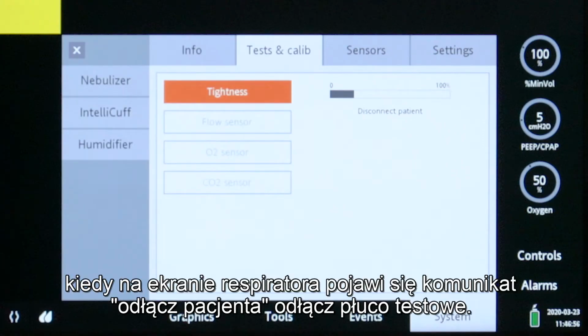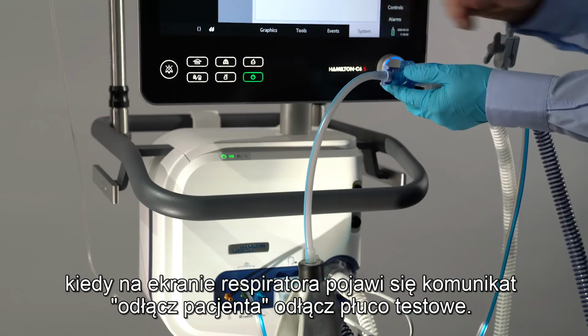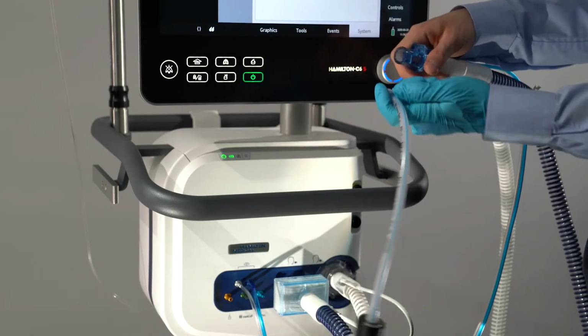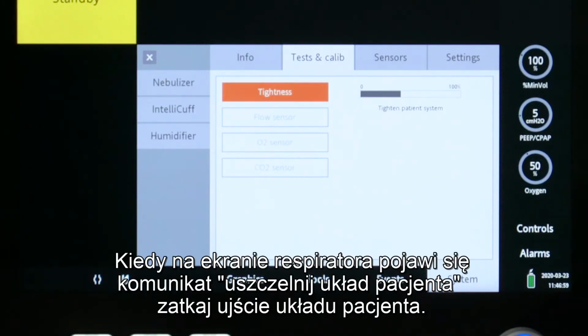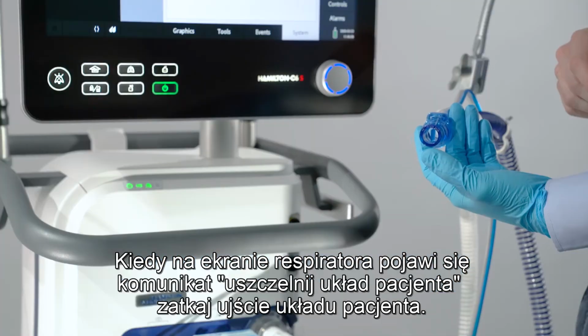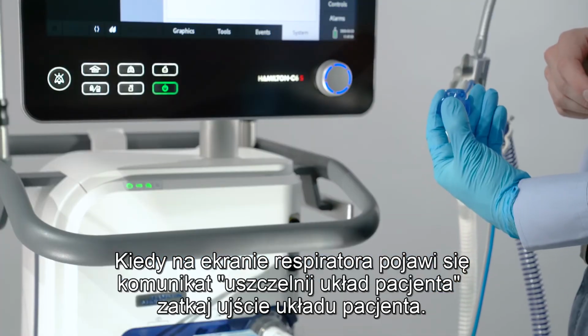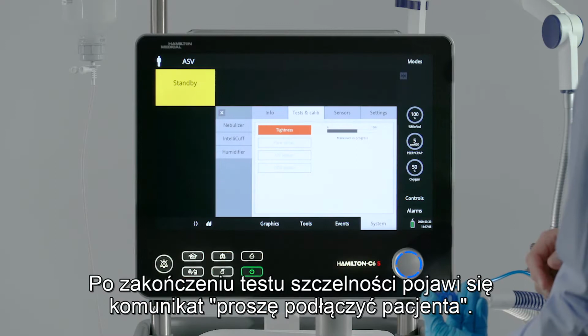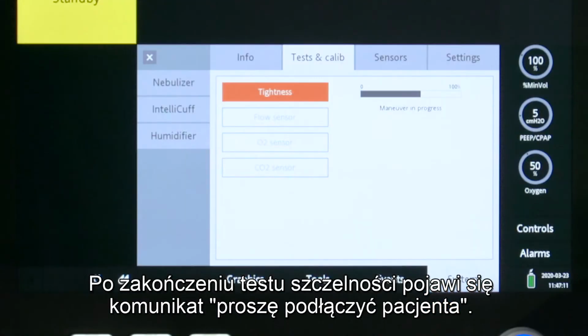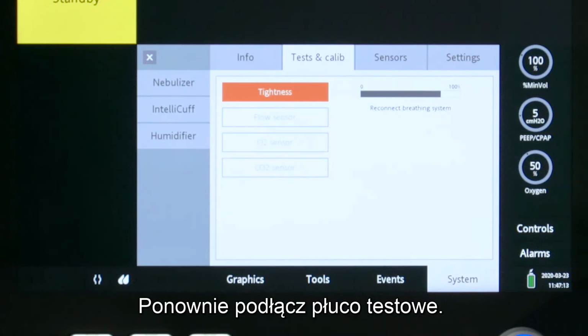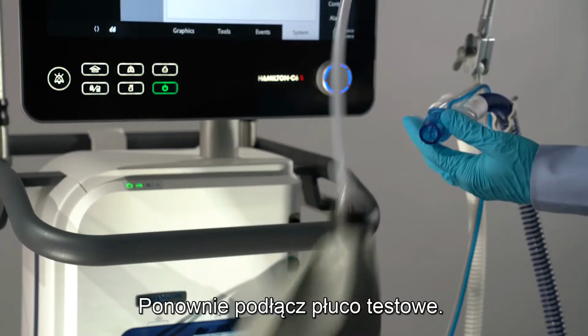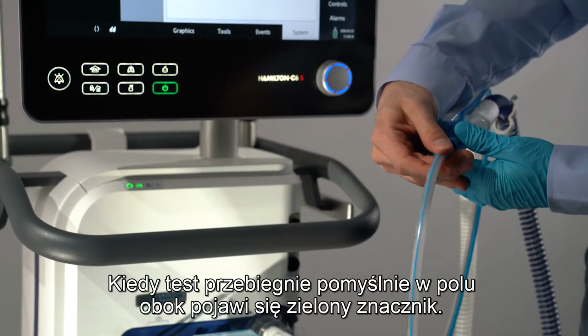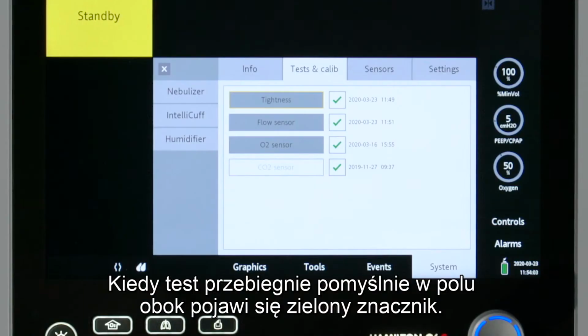When the disconnect patient message appears, disconnect the test lung. When the message tighten patient system is displayed, block the opening. After completing the tightness test, the message reconnect breathing system is displayed. Reconnect the breathing system. When the test has been completed successfully, a check mark will appear.